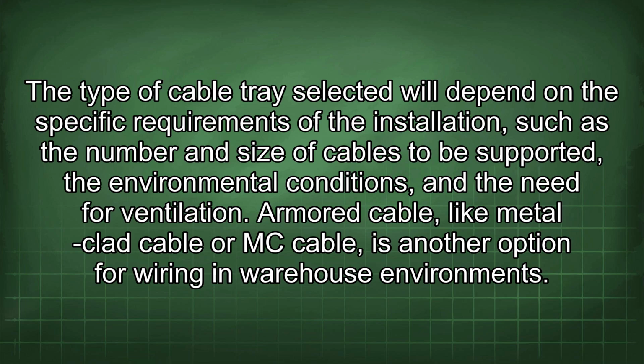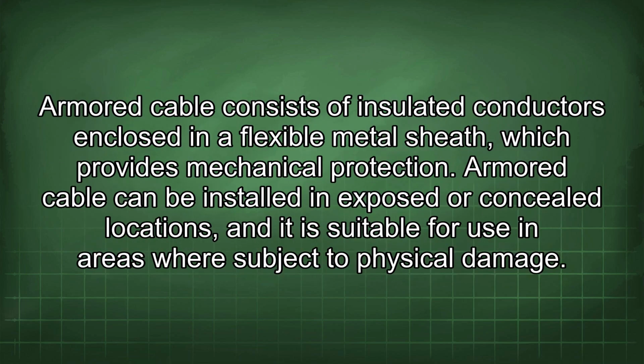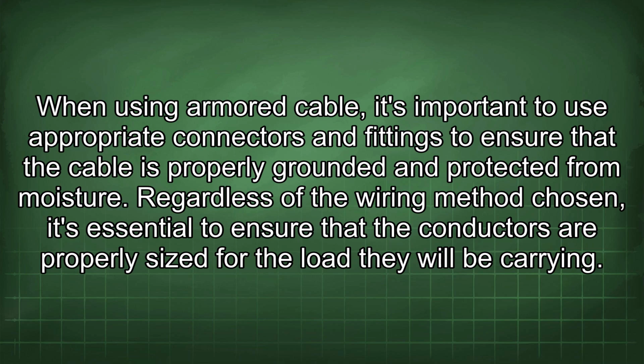Armored cable, like metal-clad cable or MC cable, is another option for wiring in warehouse environments. Armored cable consists of insulated conductors enclosed in a flexible metal sheath, which provides mechanical protection. Armored cable can be installed in exposed or concealed locations, and it is suitable for use in areas where subject to physical damage. When using armored cable, it's important to use appropriate connectors and fittings to ensure that the cable is properly grounded and protected from moisture.